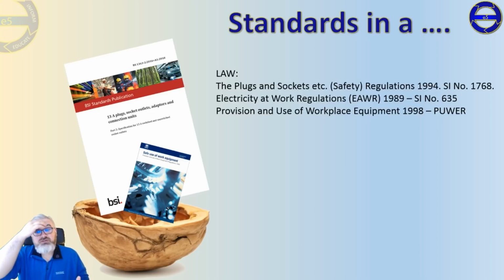However, most electricians who may not be familiar with that will look straight away and go to the Electricity at Work Regulations, EAWR 1989, statutory instrument number 635. That's the one that we as installers and inspectors are made very much aware of, because obviously Regulation 5, equipment fit for use, Regulation 8, earthing, 4, safe system of work, and then you've got the isolation ones, and competence, Regulation 16. However, there's something called PUWER, Provision and Use of Work Equipment Regulations, that sits under that.